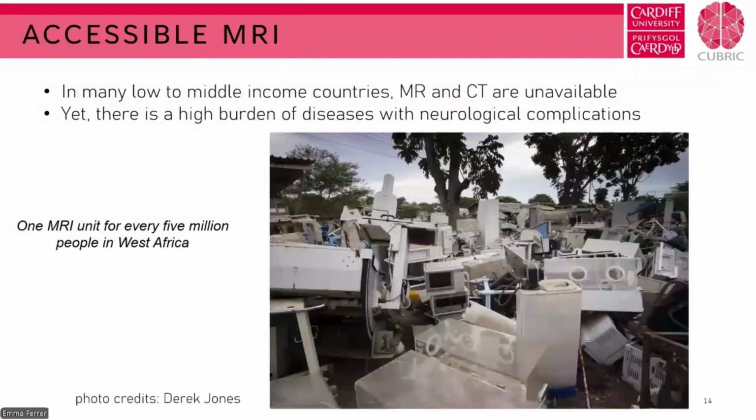And the problem is not just the cost of buying the machines, because that could be overcome with donations and so on. But the problem is that once you have an MRI machine, you need to ensure service, maintenance, power to operate it, and so on. And so this is a fairly common view in some of these countries that medical equipment gets donated, but then at the first time that it breaks down, even if it's something that would be really easy to fix in Barcelona or in London, they actually do not have access to engineers, they do not have access to parts, and so the medical equipment simply gets thrown away.